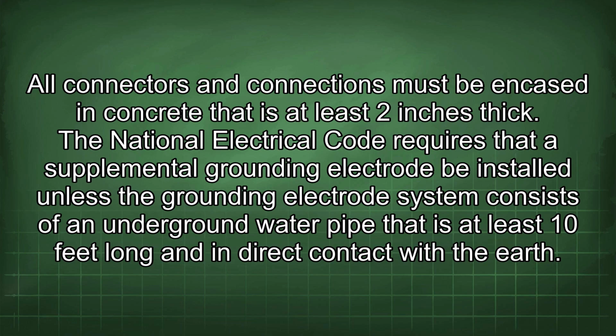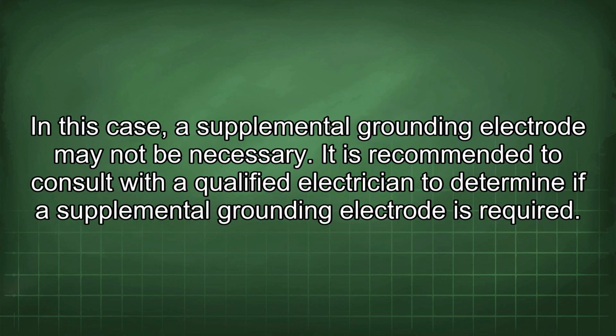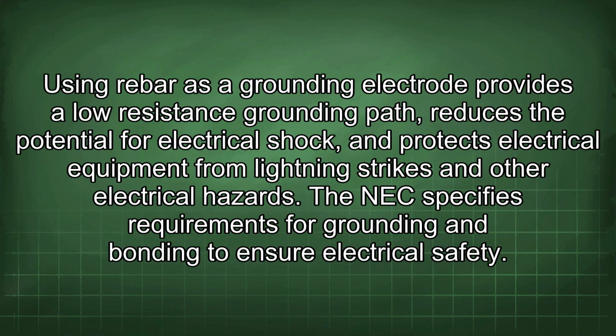The National Electrical Code requires that a supplemental grounding electrode be installed unless the grounding electrode system consists of an underground water pipe that is at least 10 feet long and in direct contact with the earth. In this case, a supplemental grounding electrode may not be necessary. It is recommended to consult with a qualified electrician to determine if a supplemental grounding electrode is required. Using rebar as a grounding electrode provides a low-resistance grounding path, reduces the potential for electrical shock, and protects electrical equipment from lightning strikes and other electrical hazards.